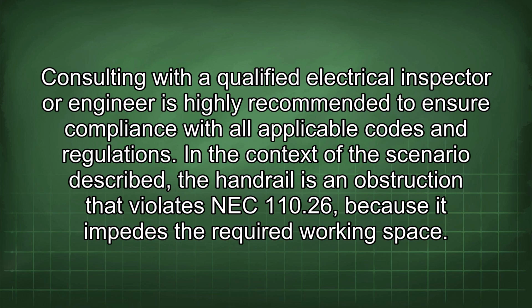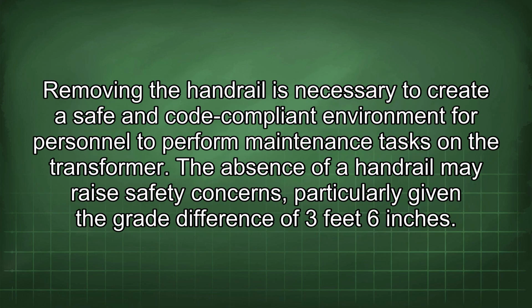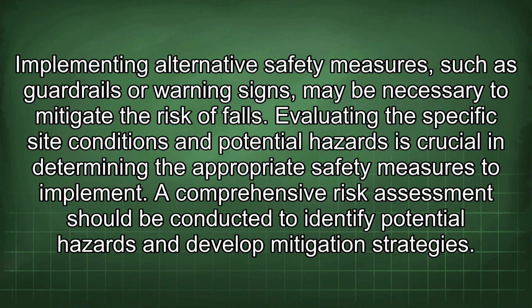In the context of the scenario described, the handrail is an obstruction that violates NEC 110.26 because it impedes the required working space. Removing the handrail is necessary to create a safe and code-compliant environment for personnel to perform maintenance tasks on the transformer. The absence of a handrail may raise safety concerns, particularly given the grade difference of 3 feet 6 inches. Implementing alternative safety measures such as guardrails or warning signs may be necessary to mitigate the risk of falls. Evaluating the specific site conditions and potential hazards is crucial in determining the appropriate safety measures to implement.